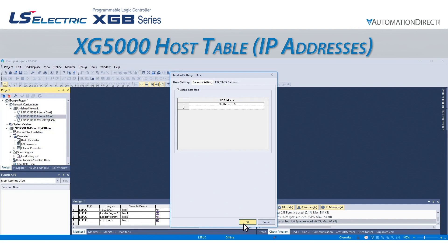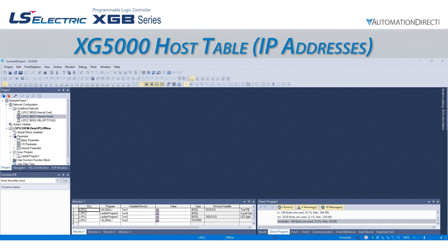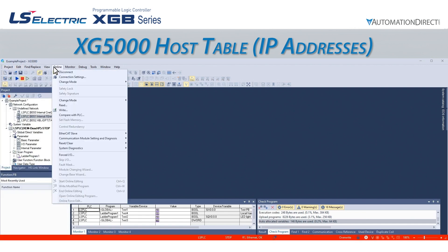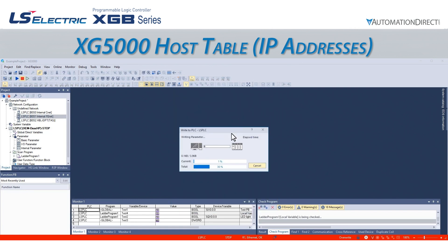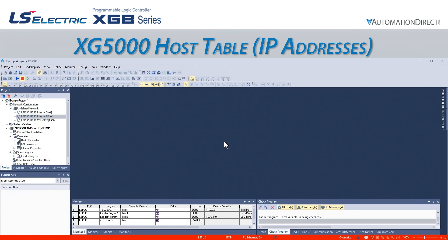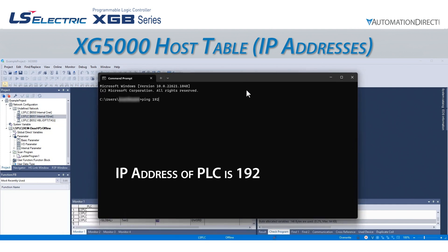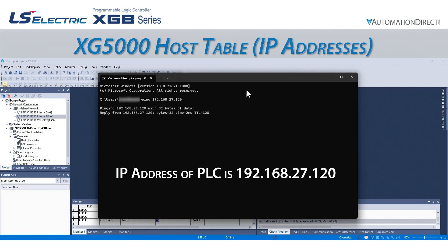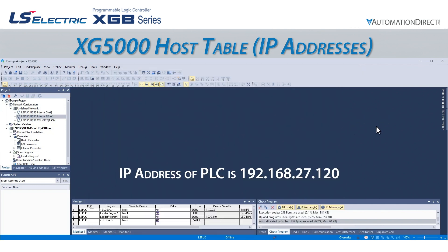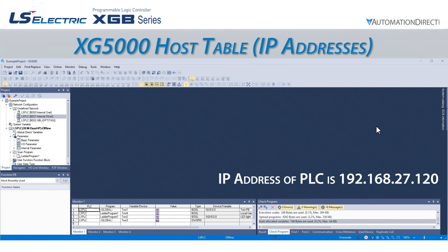If we select OK to accept the changes, we can write this to the PLC. It is important to note this applies to all incoming connections. The interface will still respond to a ping test, but it will not allow programming from a PC. It also won't allow access from an external device over Ethernet if the external device's IP address is not added to this list.